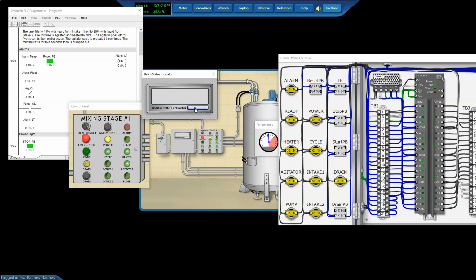It does not, just as we suspected. And we hit the high temp. So we never hit our 70, but we did hit our high temp. So we definitely got a problem there. So my next question is, what might you do next?